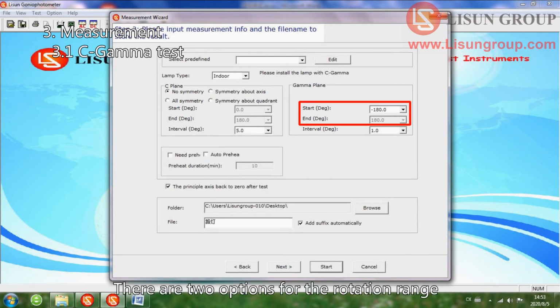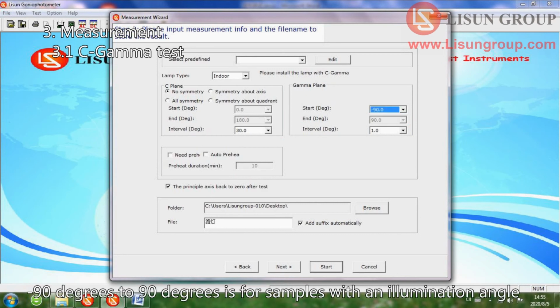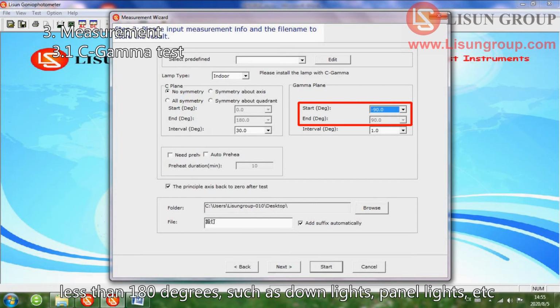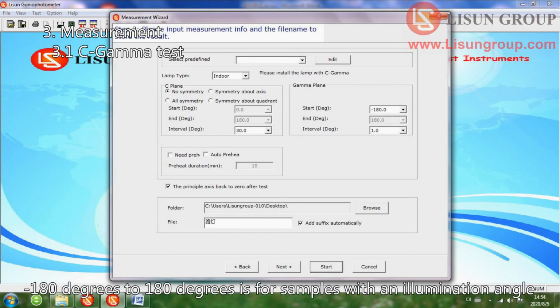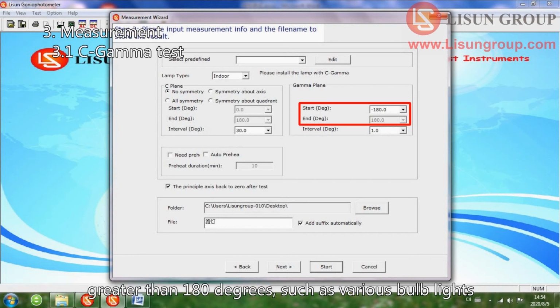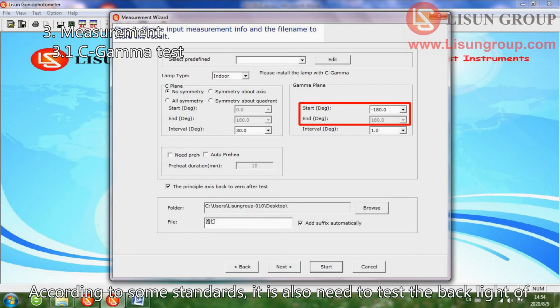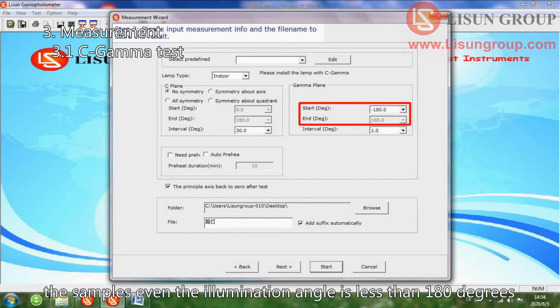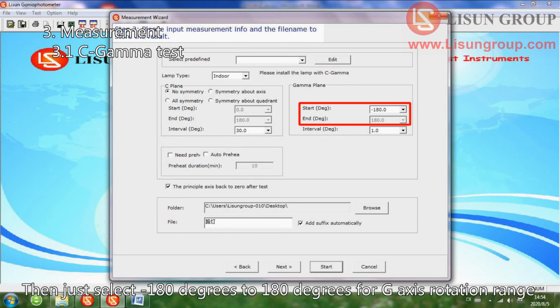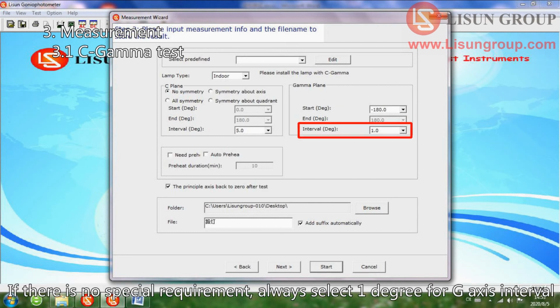G-plane. There are two options for the rotation range. -90 degrees to 90 degrees is for samples with an illumination angle less than 180 degrees, such as down lights, panel lights, etc. -180 degrees to 180 degrees is for samples with an illumination angle greater than 180 degrees, such as various bulb lights. According to some standards, it is also needed to test the backlight of the samples even if the illumination angle is less than 180 degrees. Then just select -180 degrees to 180 degrees for G-axis rotation range. If there is no special requirement, always select 1 degree for G-axis interval.